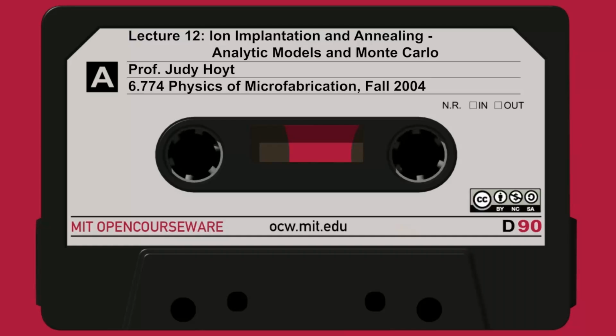So basically how this works, if you go back to any of your elementary physics classes, you know that what's happening here to the ions as they traverse this arc in the magnet is that the centrifugal force is balanced by the magnetic force, the V cross B force. So that has to be the case for ions going through this arc. And you also know the velocity of the ions coming into the arc because you know their energy, and that is set by this extraction voltage, V extraction.